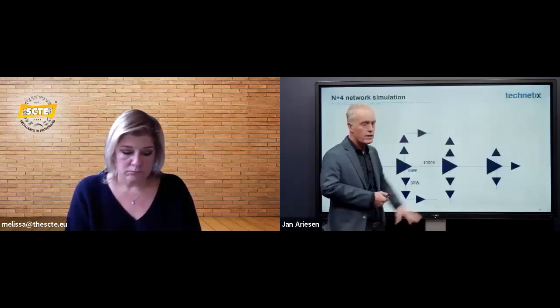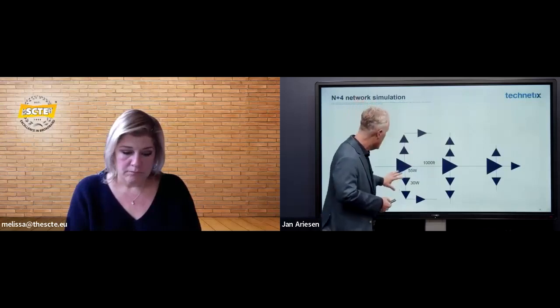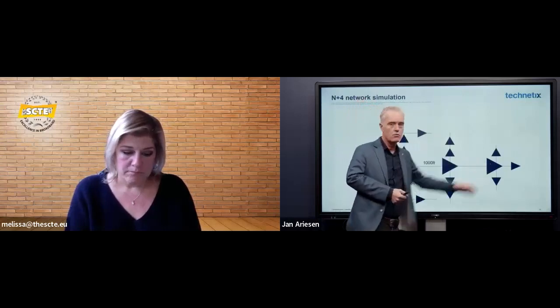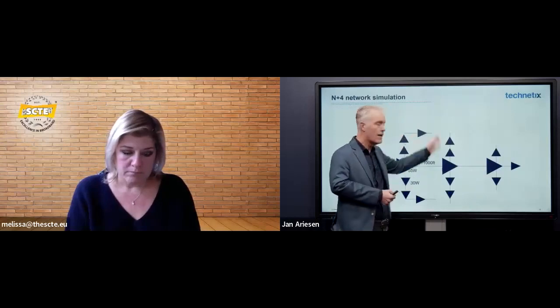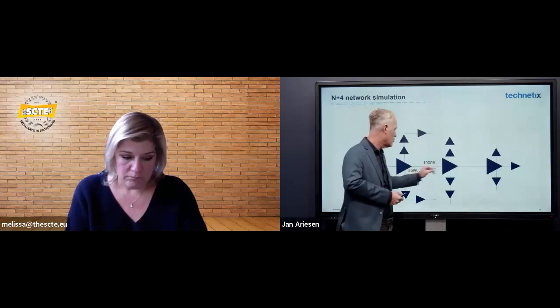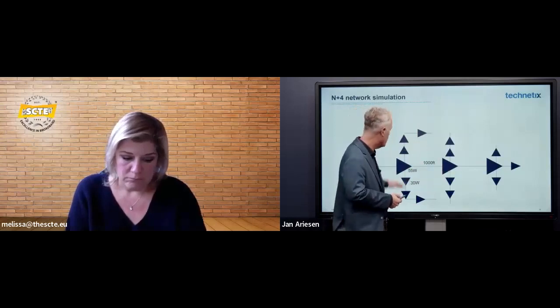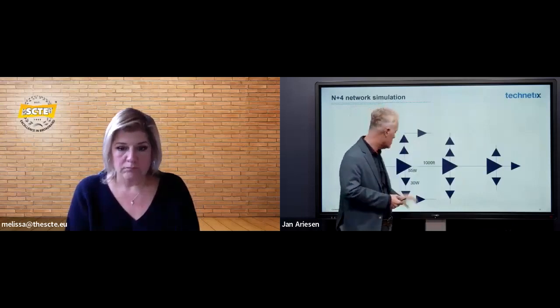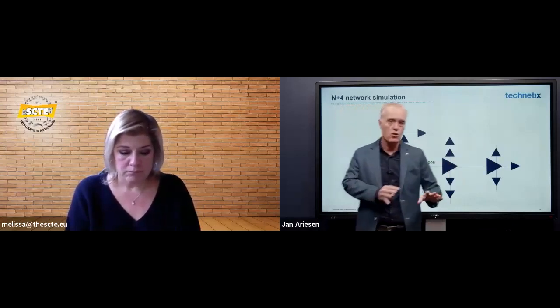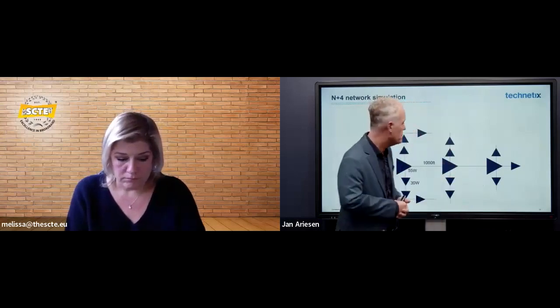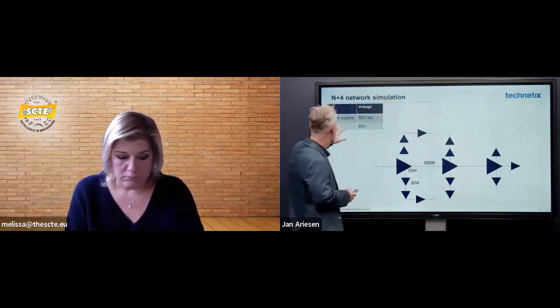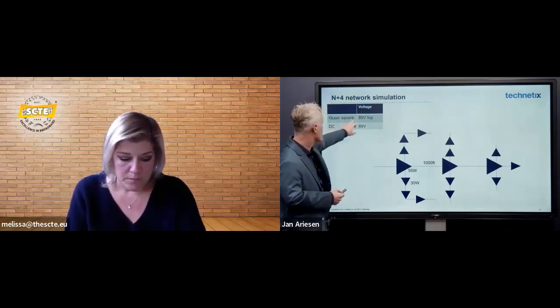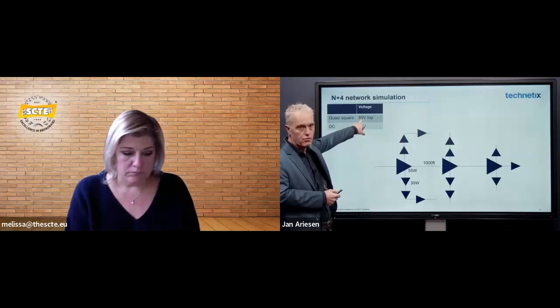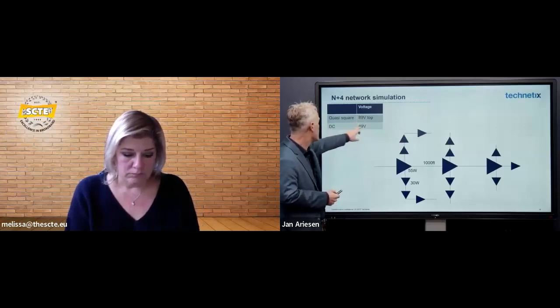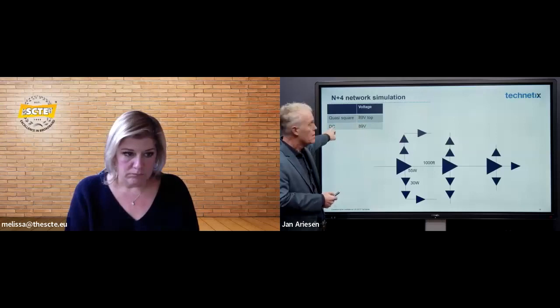So we look at a network like this, an N+4 network, where you have 3 trunk amplifiers and then a number of line extenders around it. It's about 300 meters of coax between the amplifiers, 55 watts for the bigger ones, 30 watts for the smaller amplifiers. Just a network to compare apples to apples. And what we looked into is, what will happen if I have a quasi-square 89 volt top voltage, or I have an 89 volt DC voltage? What is the impact on the network?